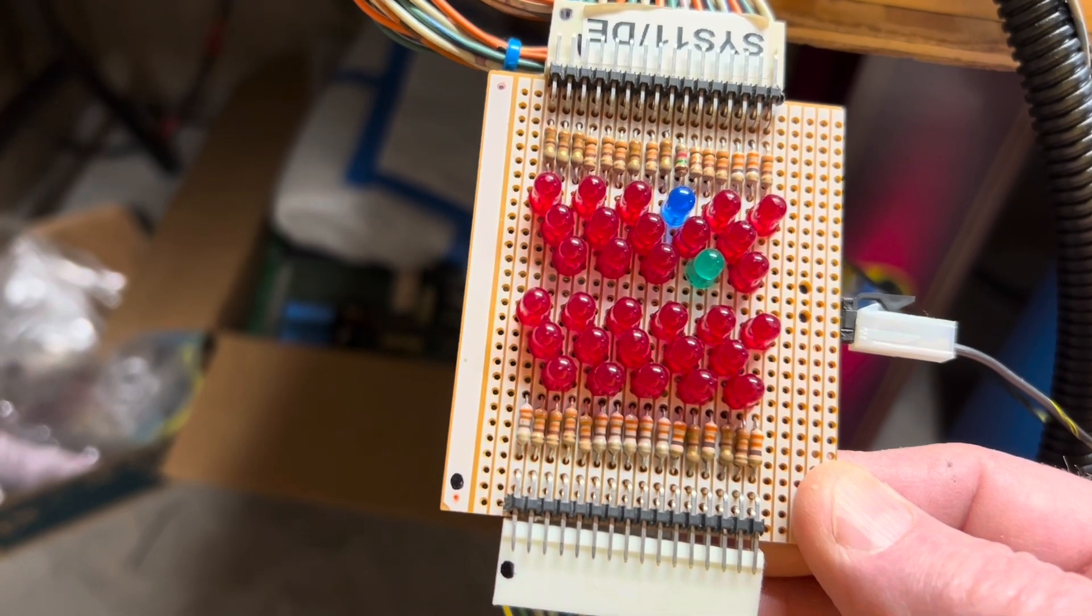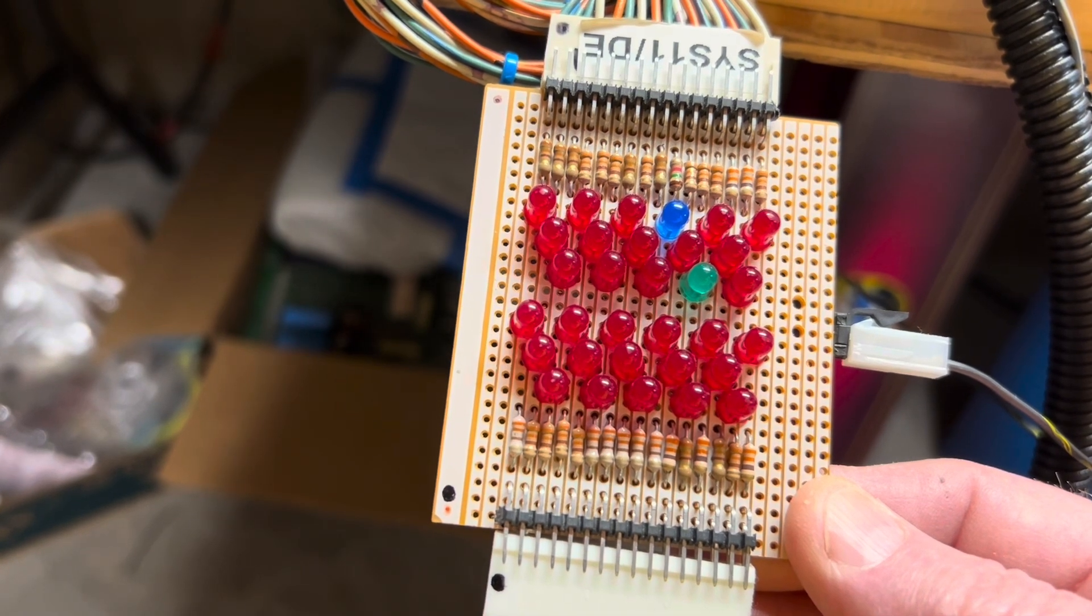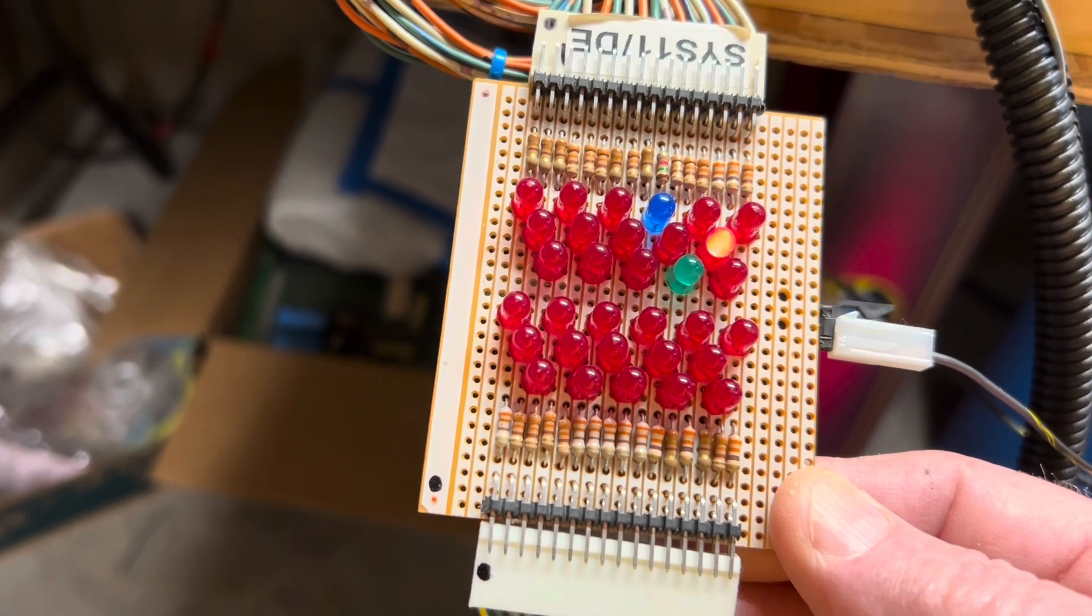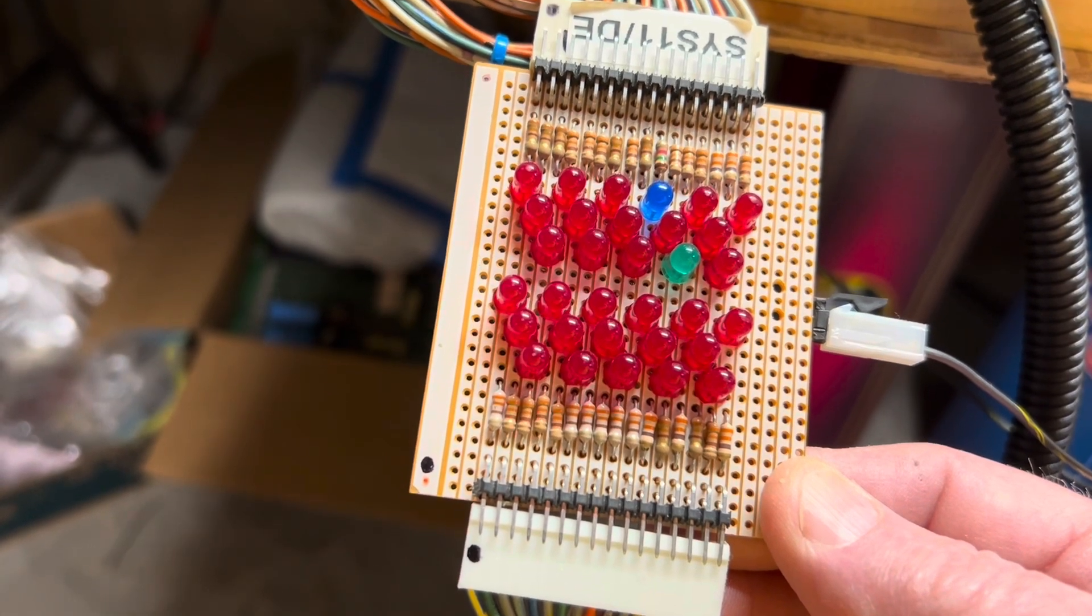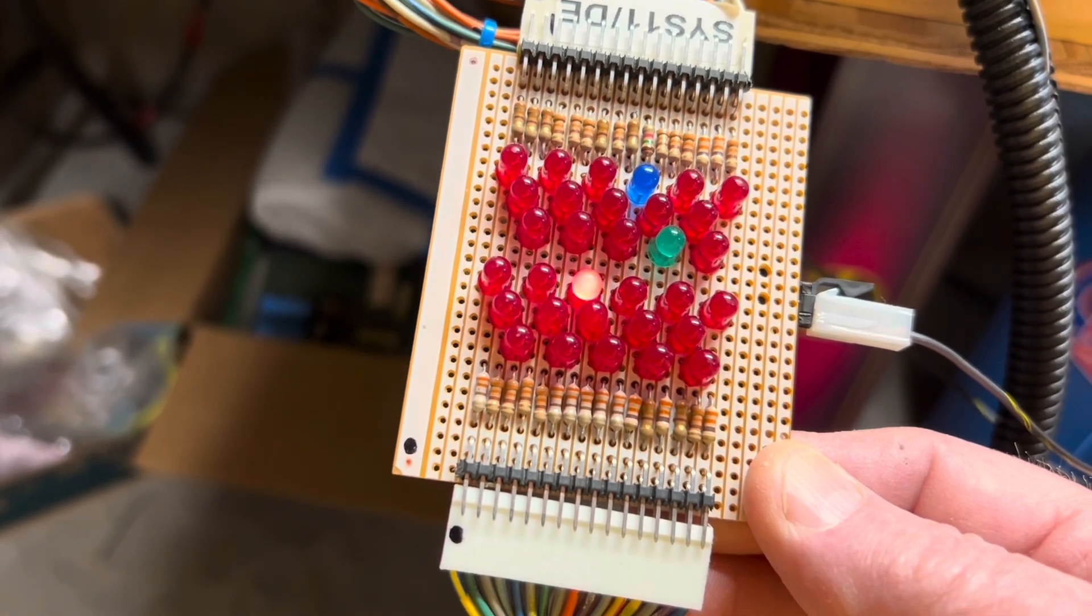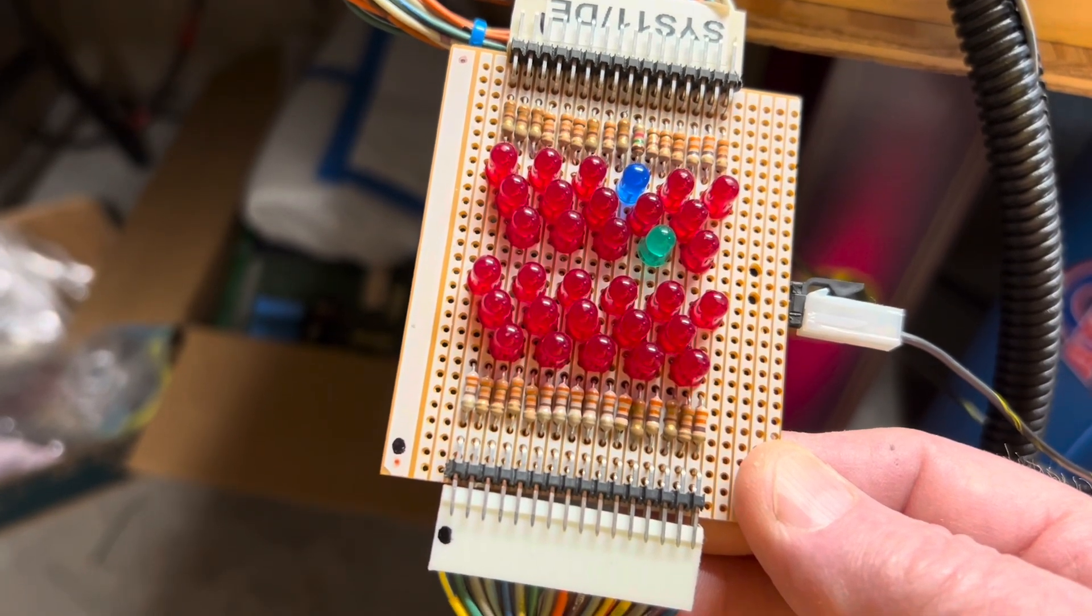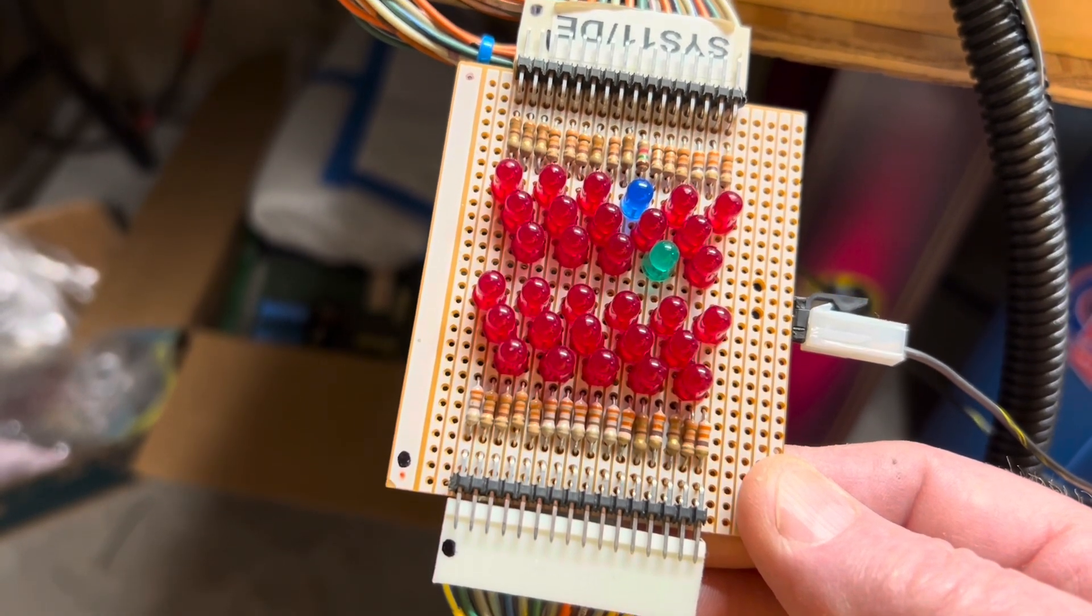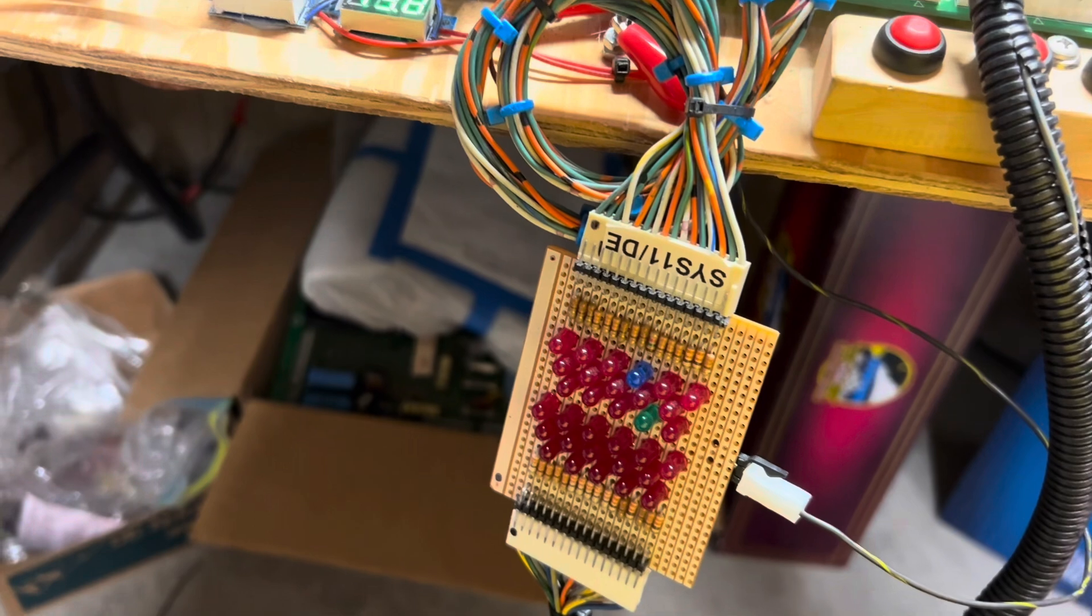You can see solenoid 2 did not work. So let me go through this one more time. I wish I could speed this part up. Maybe I'll experiment with that in post-processing. I did figure out how to put picture in picture on my videos the other day. So that was another thing new to learn. Do I make any money off of YouTube? Not a cent. No, I started that channel just to show people that their boards were working. Okay, so solenoid 2 and solenoid 32 are not working.